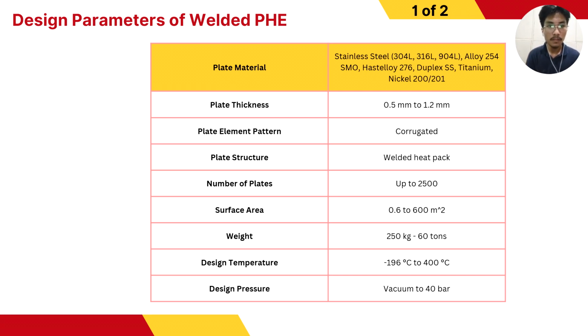Next one, design pressure. So vacuum to 40 bar. It can be utilized up to 40 bar or 4,000 kilopascal. It also depends on the manufacturers of the welded plate heat exchanger. So some would say their welded PHE can be up to 30 bar, 35 bar, and so on. So it is highly dependent on the manufacturer.